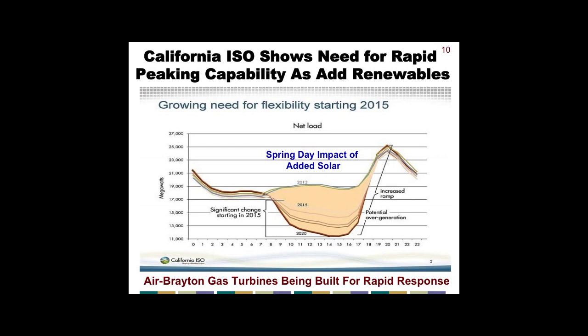And then there comes the evening. The sun, in terms of photovoltaics, begins to fall out of the sky about 4 p.m., so your photovoltaic output is going down. At the same time, everybody's turning on the lights at home and the ovens for cooking, and your power demand goes up. So the 2020 projection for California is that the non-photovoltaic power plants will need to roughly double their output in approximately 2.5 hours every day around 5 o'clock. This is going to be an exciting grid.